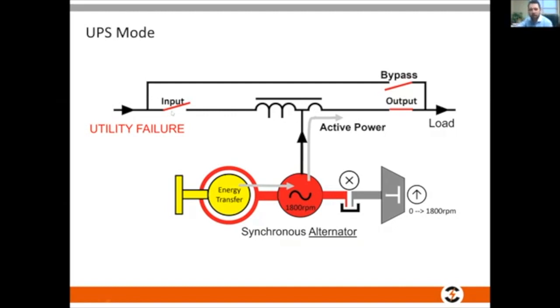But when the input breaker opens, my alternator was already instantaneously at 1800 RPM, which, as you know, is the speed for a static UPS that you wait for the diesel generator. I'm not waiting, my alternator was already there. The challenge is to maintain it.